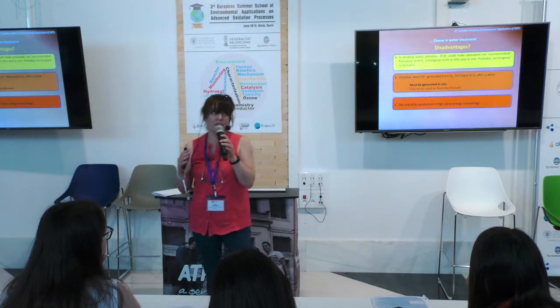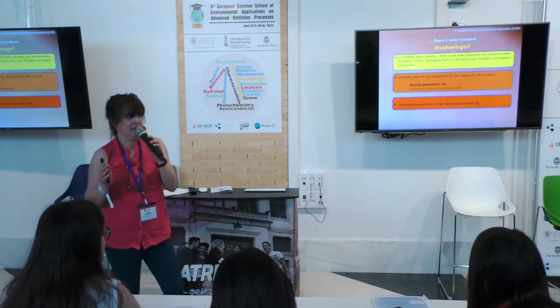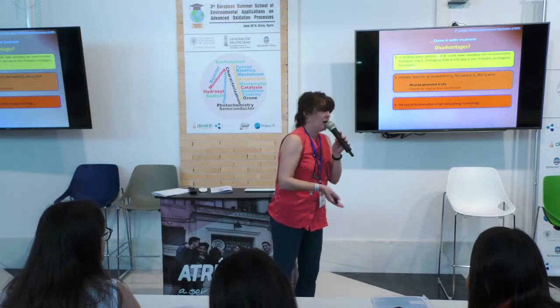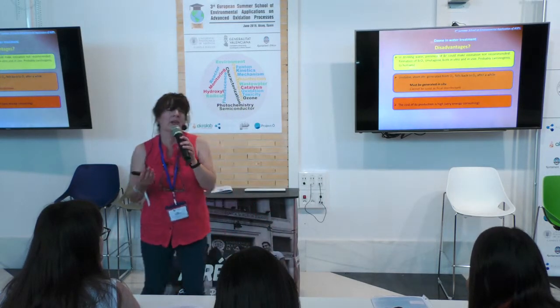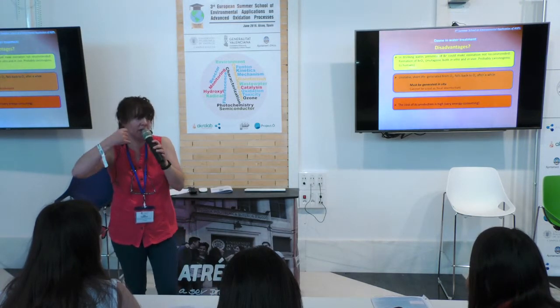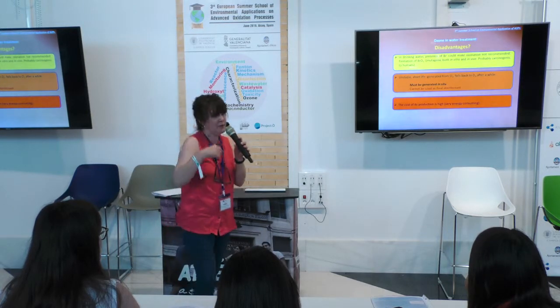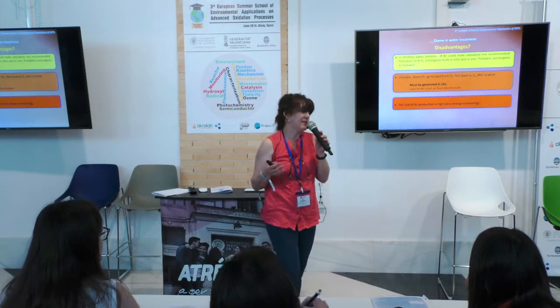Another more important disadvantage is that ozone is very unstable, has a very short life. So it is formed from oxygen and falls back to oxygen after a while. It implies that it must be generated in situ. You cannot pick up the phone and say, please send me a balloon of ozone, no. So you have to obtain it in situ and it cannot be used as a final disinfectant.